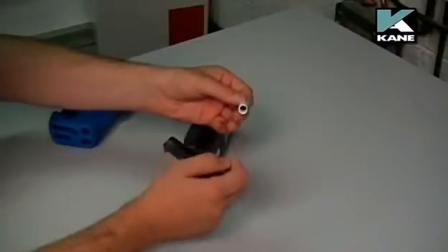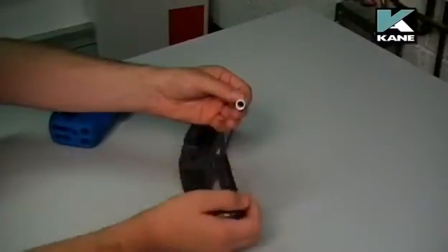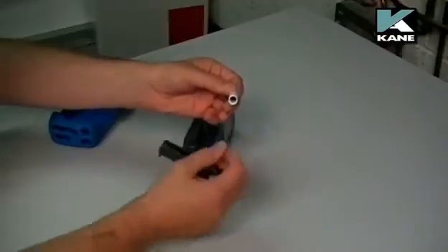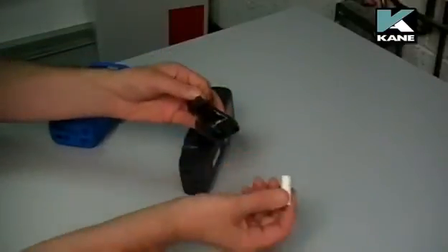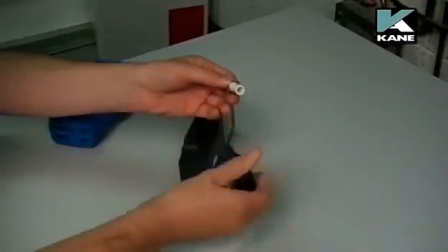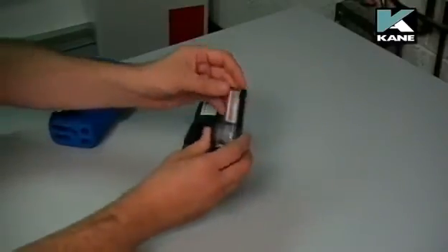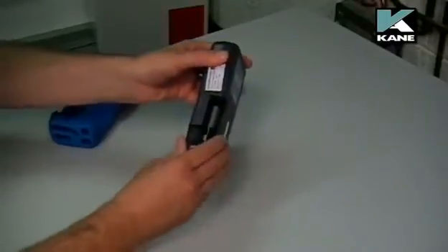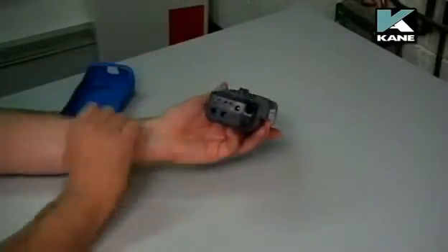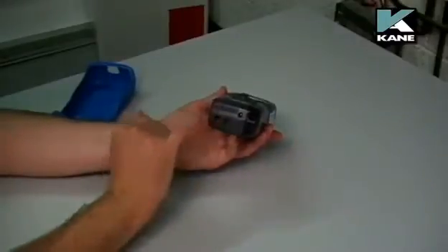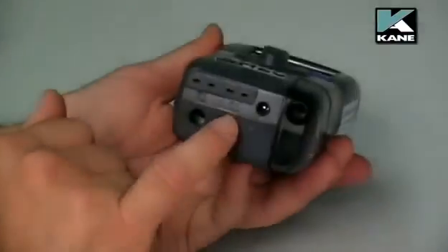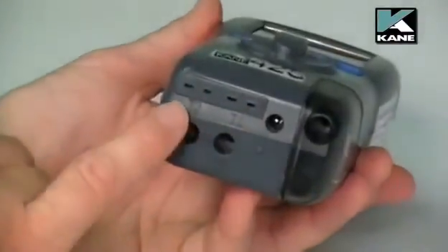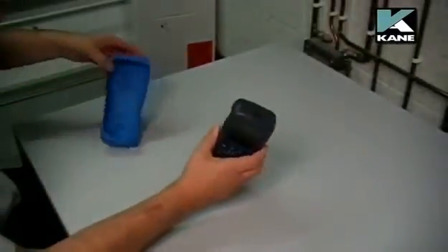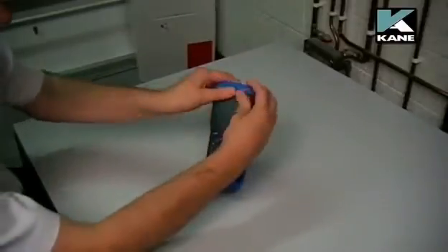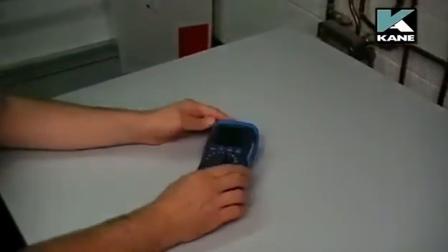It's actually the middle of the filter that gets dirty first. So if that filter was blocked, dispose of this filter, replace it with a new filter and reassemble. Also, while we've got the rubber boot off, you can also see on the bottom of the instrument these connections are actually marked up as T1, T2, P1 and P2. Just replace the rubber boot, push it in at the bottom, pull it up at the top, and there you go.